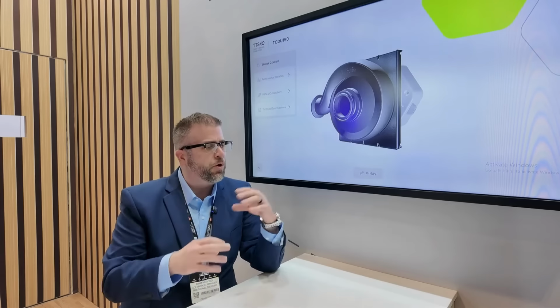So now there's not as great a power draw. We're looking at more sustainable options, even focusing on low GWP refrigerants. And that combination is helping us not just within the liquid cooling space on in-rack solutions, but also within row solutions with larger requirements, specifically the RT series, which is much more geared towards high pressure, lower flow, where the water-based TCDU units are more geared towards higher flow, lower pressure. So we're trying to take both a top-down and a bottoms-up approach and find that sweet spot in the middle, whether it's high pressure, low flow, low pressure, high flow, or whether you're looking for refrigerant or water-based cooling solutions. We're trying to expand that portfolio to cover the breadth of the market demand.